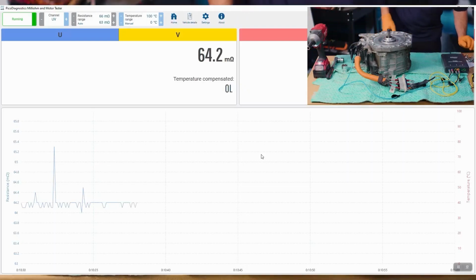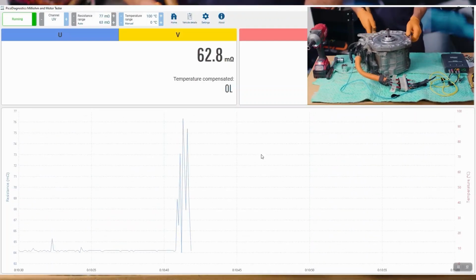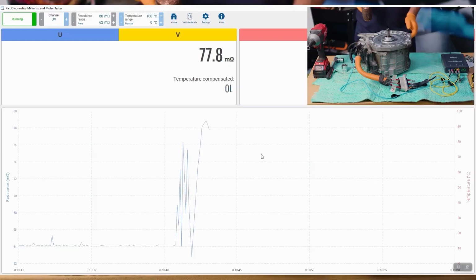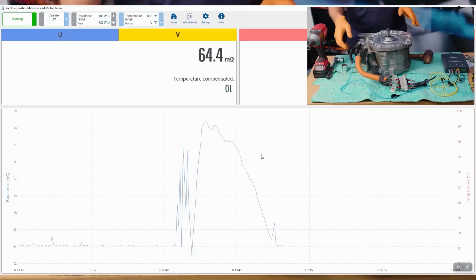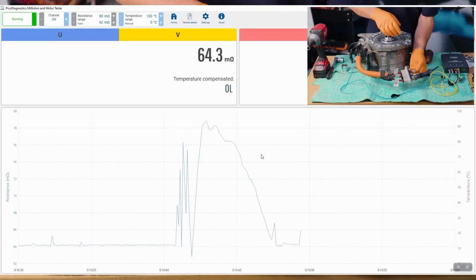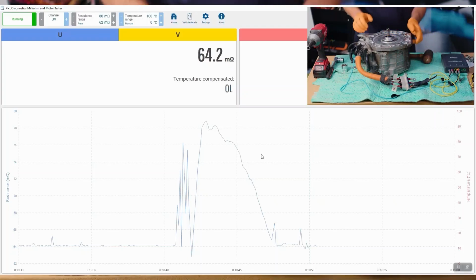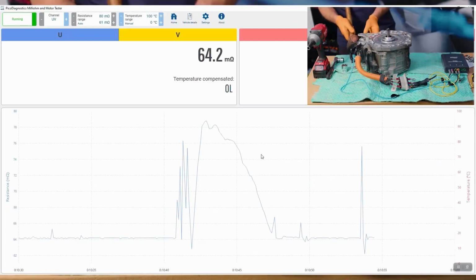Still at 64 milliohm. We'll just give that a tap and see if that changes our resistance. That's a good sound. Now then, that is interesting. We've gone up to 76, which ironically, 77 was the other values. And nothing is changing. This is still gripped here. Gone back down to 64. This is still a good connection here. It does have an effect, it appears.